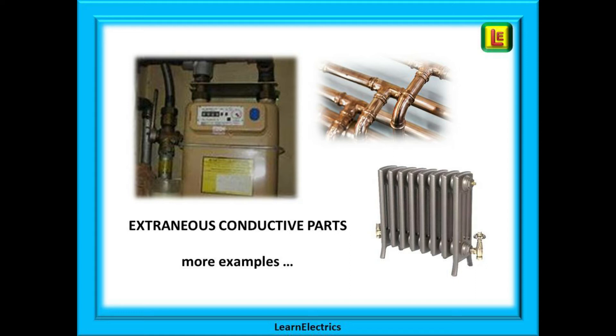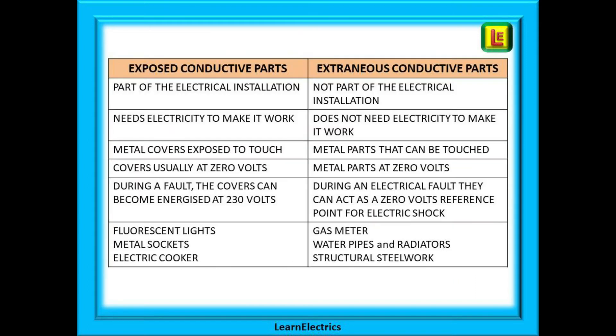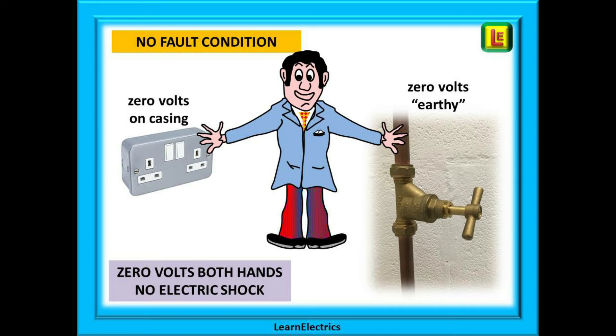Other examples of extraneous or earthy parts typical of domestic installations are shown here — for example, a gas meter, water pipes, and a central heating radiator. We have also shown the differences between exposed and extraneous parts side by side in a chart. The main thing to take away is that exposed conductive parts have electricity going to them; extraneous parts do not. It is the earthy nature of extraneous parts that introduces the danger.